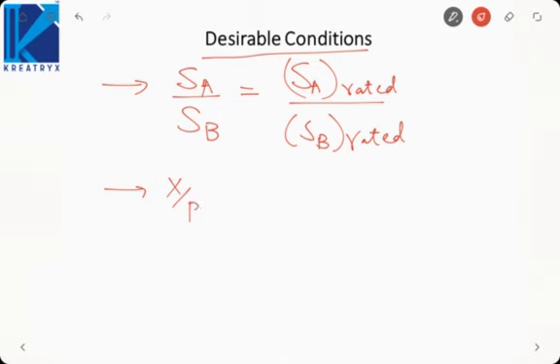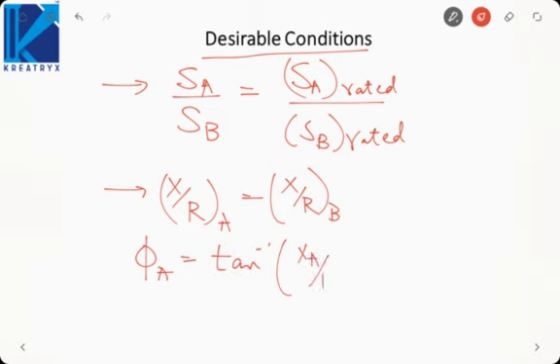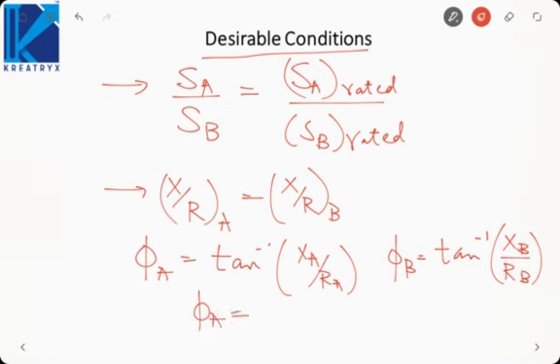Next is X by R of A must be equal to X by R of B. Reactance to resistance ratio of both the transformers must be same. Why? Because phi A, the power factor angle, is tan inverse XA by RA and phi B will be tan inverse XB by RB. Now if both X by R are same, phi A is equal to phi B, power factor angles are equal, or we can say power factors are also equal. So if you want to operate both the transformers at equal power factor, their X by R ratio must be same. That is a desirable condition but not a necessary condition. Is it fine?